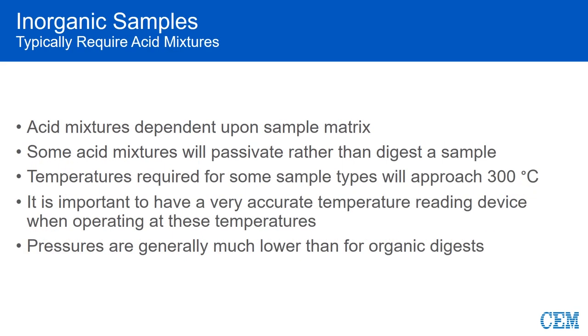Inorganic samples are more complex and will require different acid mixtures in order to provide a completely digested sample. Some inorganic materials will require temperatures as high as 300 degrees C in order to get a total digest. Inorganic digestion is more complicated than organic digestion. Fortunately, we have developed method notes to cover a vast majority of these applications.